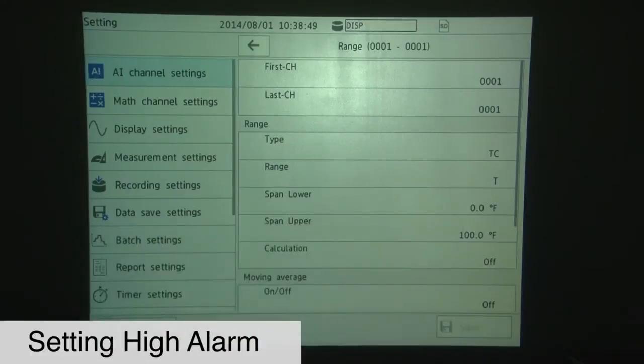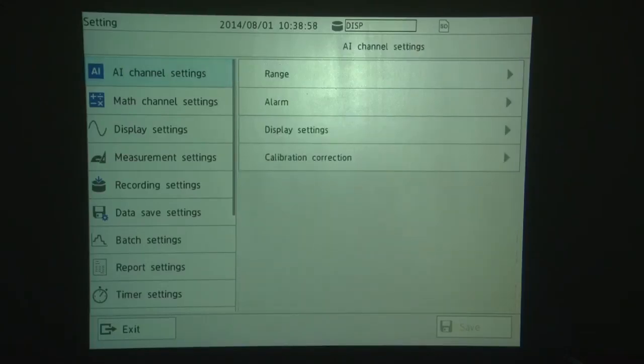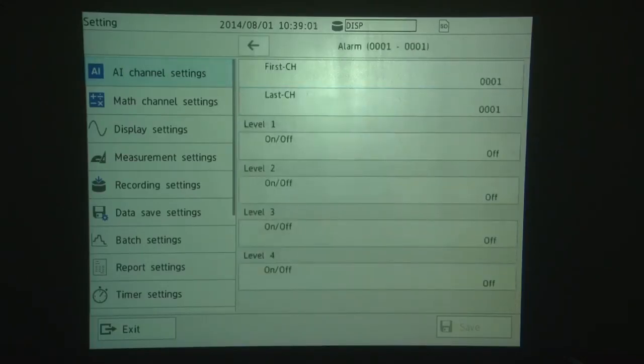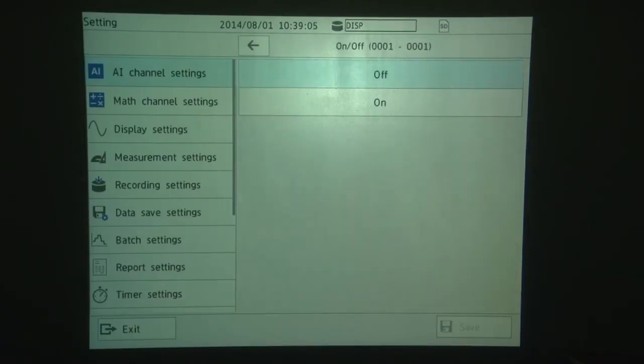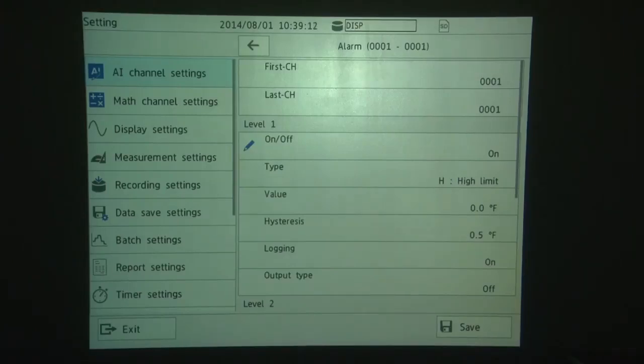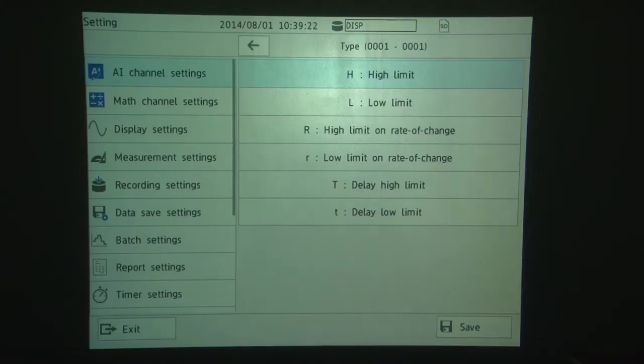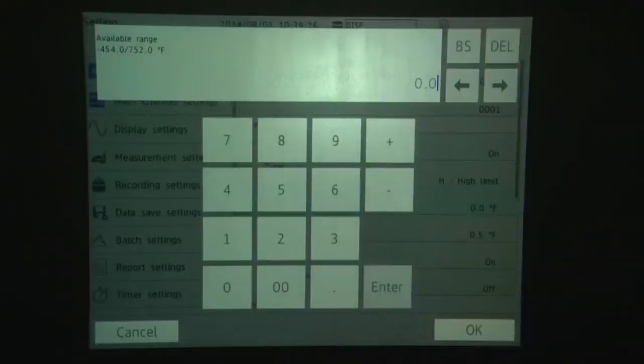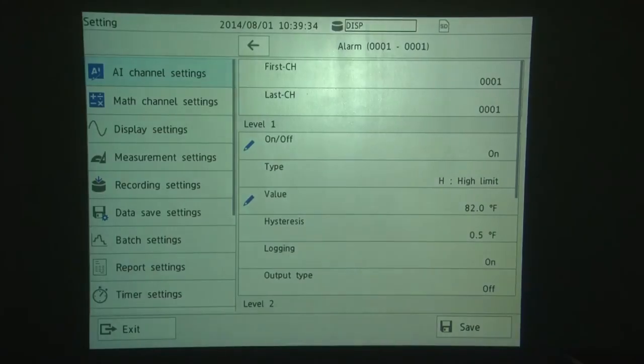The next thing we'll do is set a high channel alarm for, or set a high alarm for Channel 1. So back here in the AI Channel Setting menu, we touch Alarm. We're going to go to Alarm Level 1. Set that to On. We're going to choose a High Alarm, which is the first alarm in the list. And you'll see High Alarm, Low, or High Limit Alarm, Low Limit, Rate of Change High, Rate of Change Low, Time Delay High, Time Delay Low. So we're going to use a high alarm. And we're going to set a value of 82 degrees. And then touch Save.